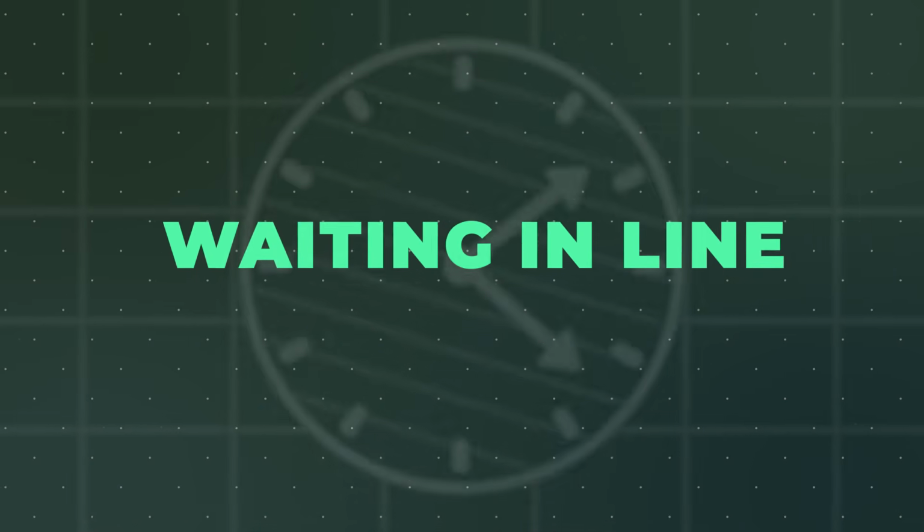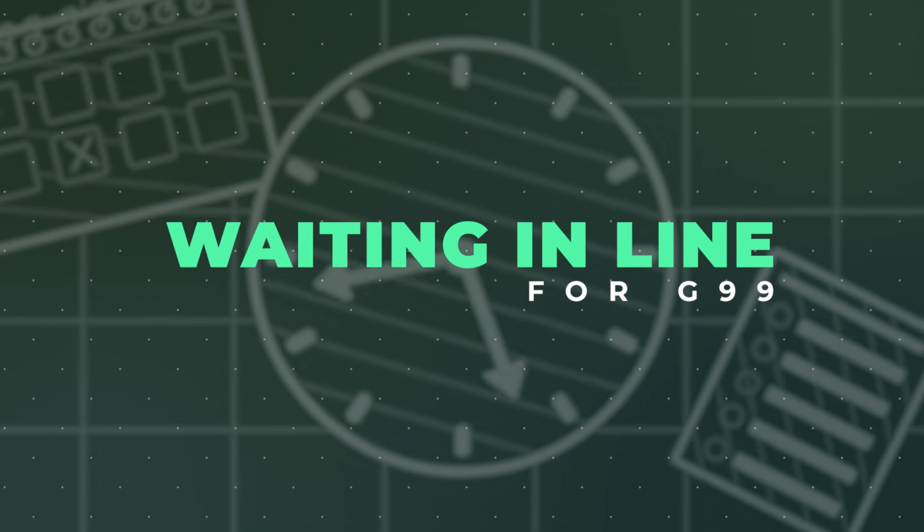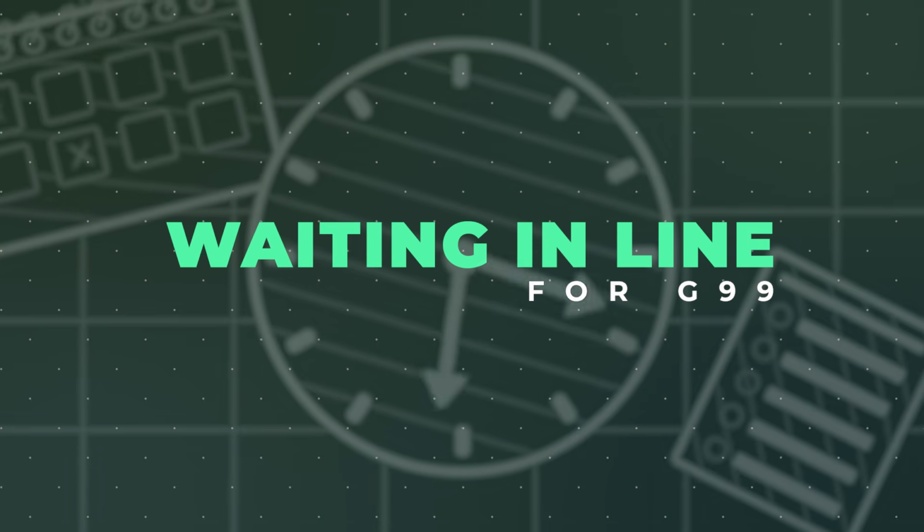However, with a G99, we have to get a pre-approval in place. So we write out to the national grid and then we go on hold music. Different network operators work on different timescales. Some are really quick that we deal with, a couple of weeks, but most of them can take up to 45 working days in order to return the application. We then get an offer letter back that basically says, this is how much we can allow you to export onto the grid. But I'll come back to that in just a second.